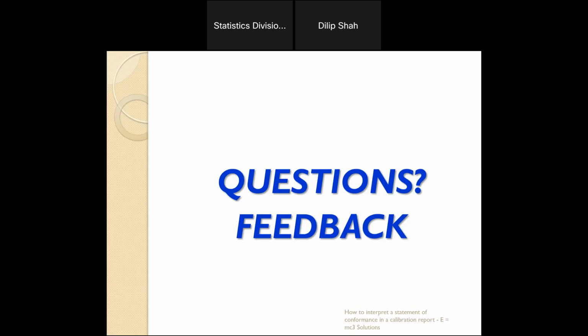So uncertainty is always reported as a normalized distribution. The uncertainty contributors itself may not be normalized, but before you combine them, you normalize them, and that GUM, the document I referenced, has guidance on how to do that.